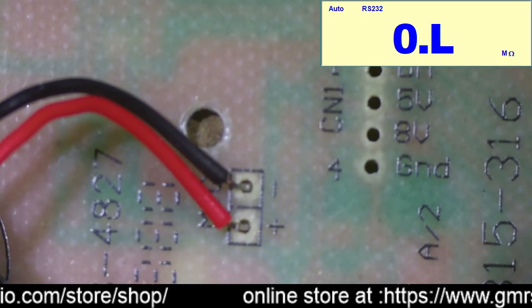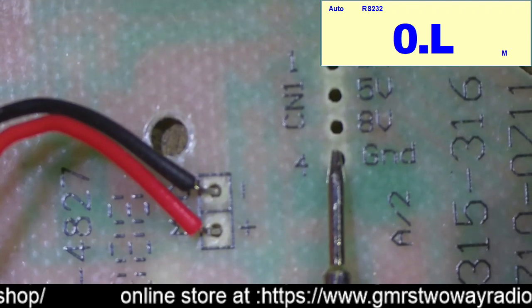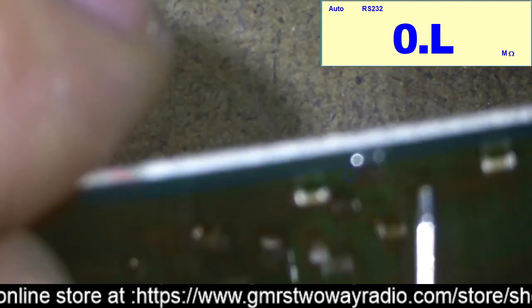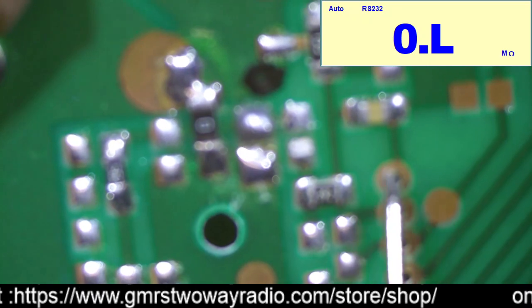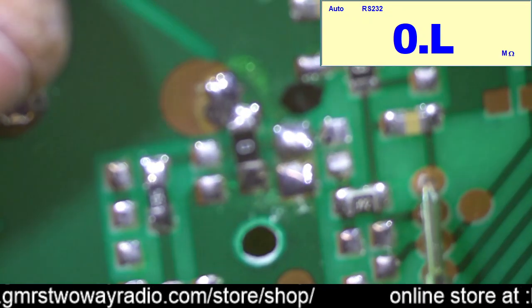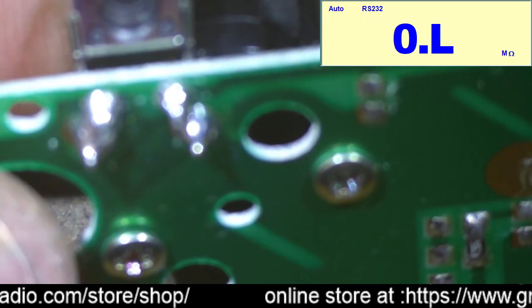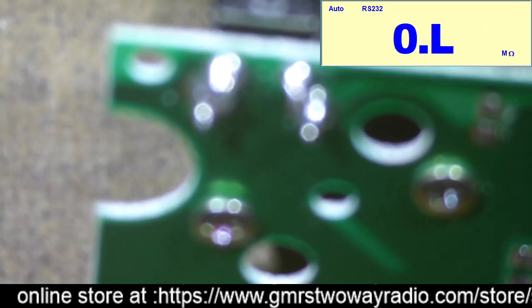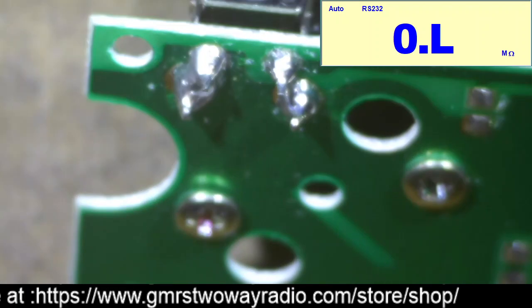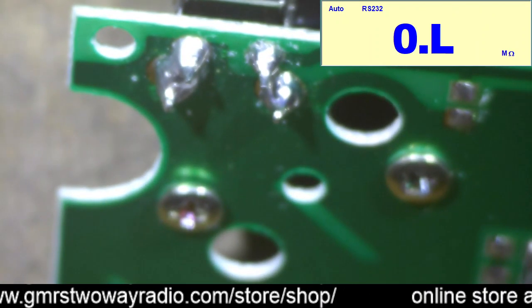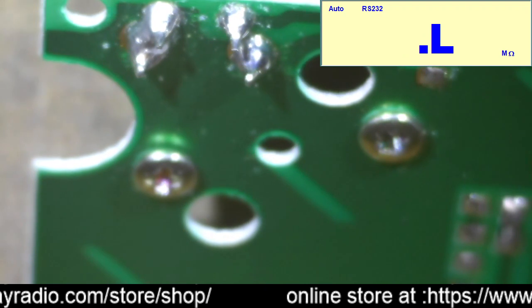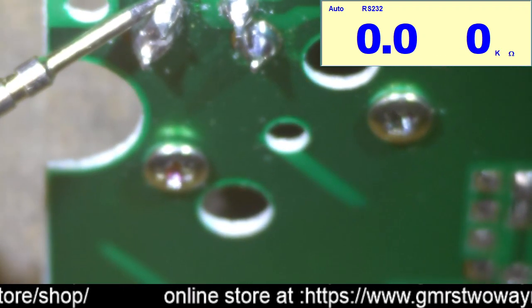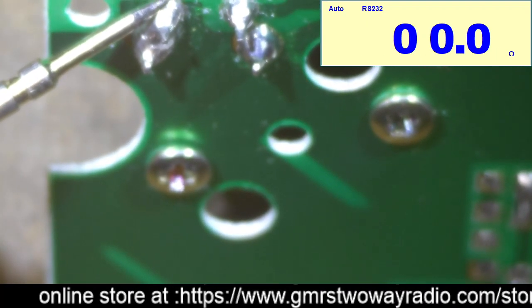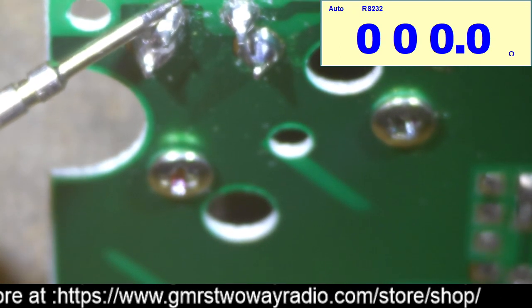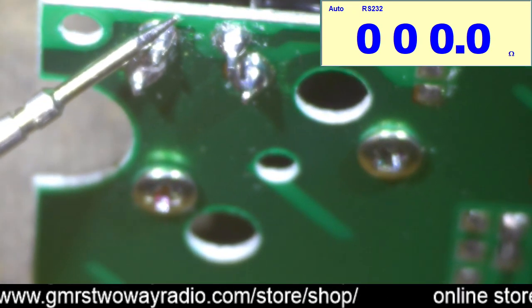With that being ground, I take my meter, flip the board around to the top one, put one probe there, and touch the other probe to the other side of that switch. If I touch it here, I have continuity, my meter reads 0, so I know that's a ground connection and that end goes to ground.